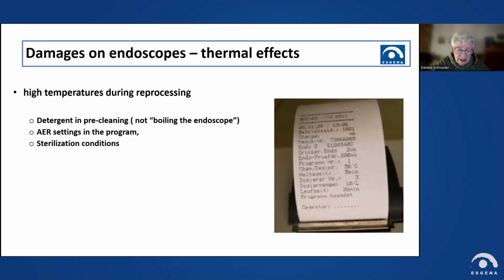What I saw once is that the detergent might also need a special or dedicated temperature. In one country, they tried to prepare the detergent solution and switched on the tap water, and it was, I think, more than 50 or 60 degrees. So they boiled the endoscope. This could be a thermal effect. So we had black spots in it.